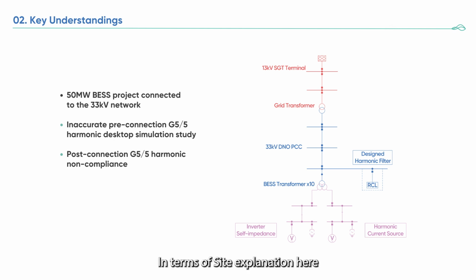In terms of site explanation, this is a 50 MW BESS project, which is quite typical in the UK, connected to a 33 kV network. The 33 kV connection point is owned by the DNO. Then the 33 kV network is connected to the 13 kilovolt super grid tertiary winding. It means that this tertiary kV system is isolated by the transmission system, and the network is heavily reactive. This is one of the reasons the harmonic non-compliances appeared here significantly.